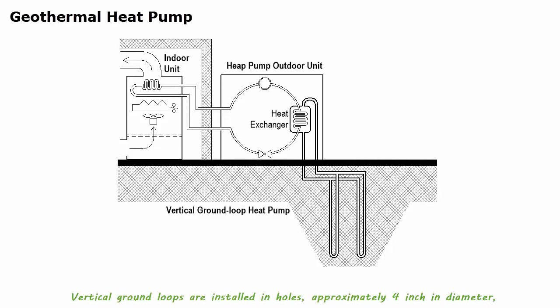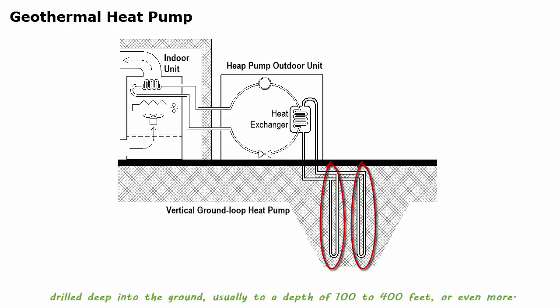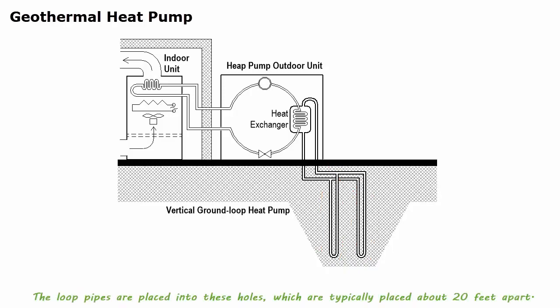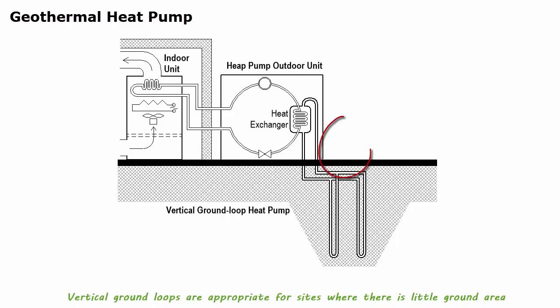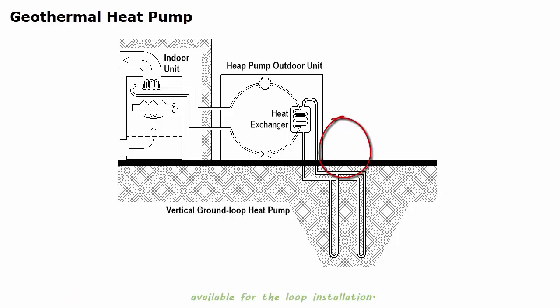Vertical ground loops are installed in holes approximately 4 inches in diameter, drilled deep into the ground, usually to a depth of 100 to 400 feet, or even more. The loop pipes are placed into these holes, which are typically placed about 20 feet apart. Vertical ground loops are appropriate for sites where there is little ground area available for the loop installation.